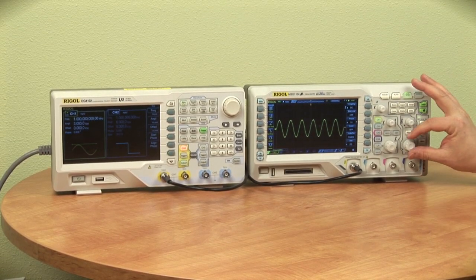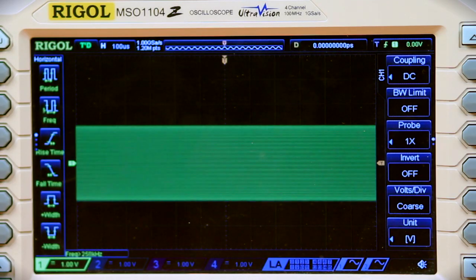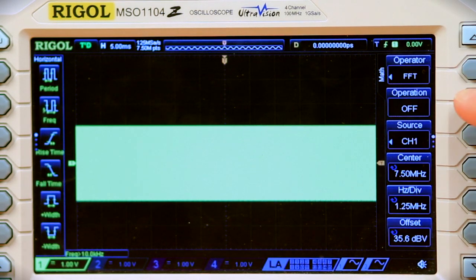Now to use our deep memory mode, the first thing we're going to do is move out the time scale on this scope. That will give us a lot more data to analyze when we do the FFT. Now let's turn the FFT on.